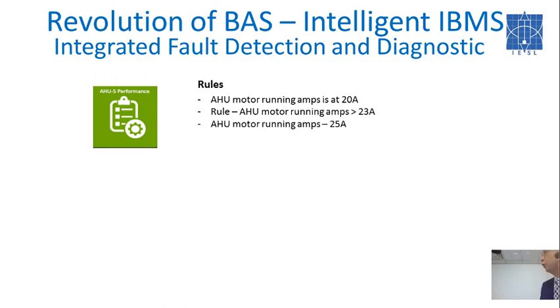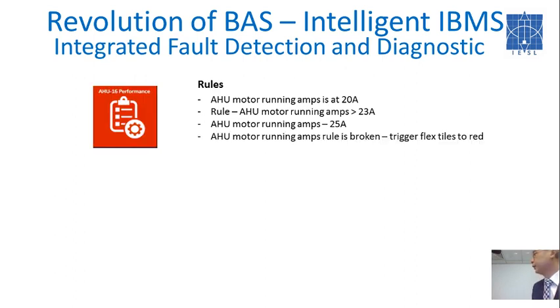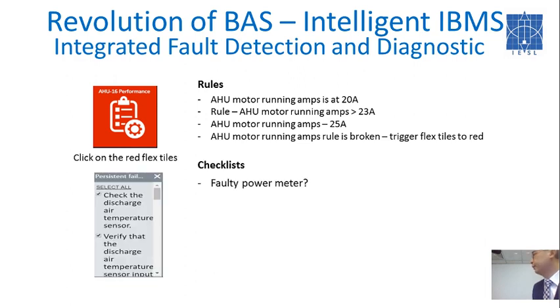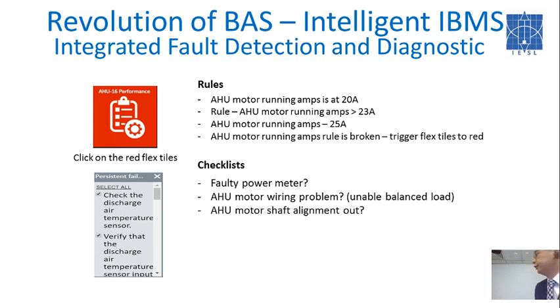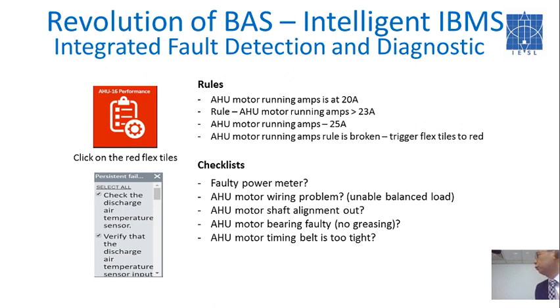So currently my AHU motor is running at 25 amps. So what will be the conditions? Right? Change to red. I'm a technician, I click on the red flex tiles. The checklist appears. It's a power meter fault. Is it the AHU motor wiring due to unbalanced load? Is the AHU motor shaft out of alignment, which causes friction itself and causes high amperes? Is it the AHU bearing fault, no greasing, no maintenance? Is the AHU timing belt too tight?